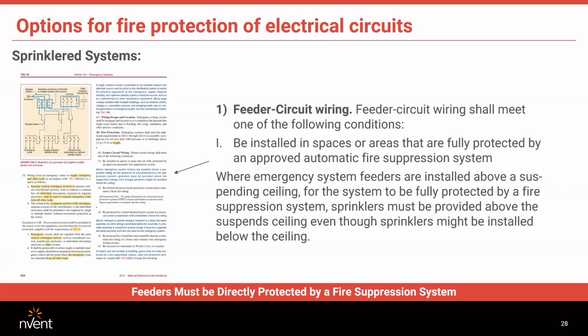And actually, not long ago, I had a situation down in Hartford, Connecticut, where the building was sprinklered, but it was not protecting the emergency feeders. And the inspector called out the contractor and the engineer, and they ended up installing MI cable because the sprinkler system was not directly protecting the feeder. So in most of my years of experience on this job, which are many, very rarely do you have a situation where the emergency feeder is protected for the entire length of the run. So more often than not, with an emergency feeder, you're going to be using fire-rated MI cable. For fire pumps, for a fire pump feeder, it doesn't matter about height, occupancy, sprinkler, no sprinkler. All fire pump feeders, regardless of height or occupancy, or whether the building is sprinklered or not, or whether the feeder is directly protected or not, they all have to be fire rated for 2 hours.